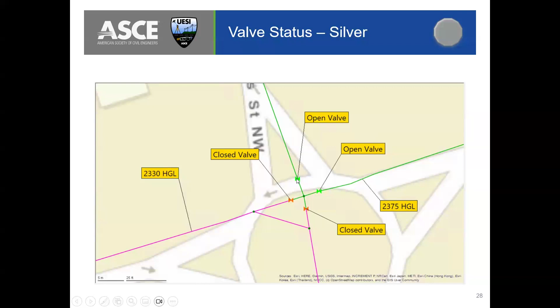What's important here is we now know the status of these valves. They are closed, so that's allowing this flow to go this way—it's not allowing the flow to bleed into the 2375—and these valves here are open. That's very important information to have.